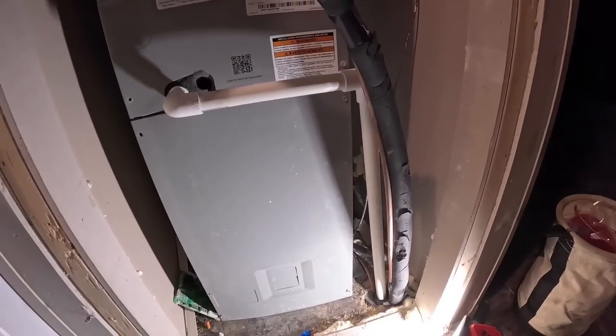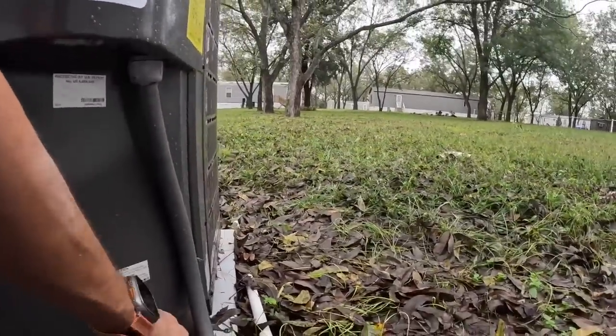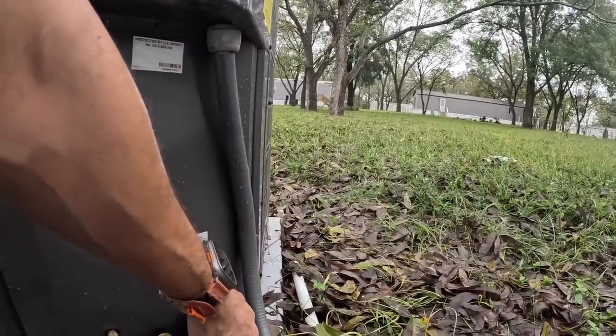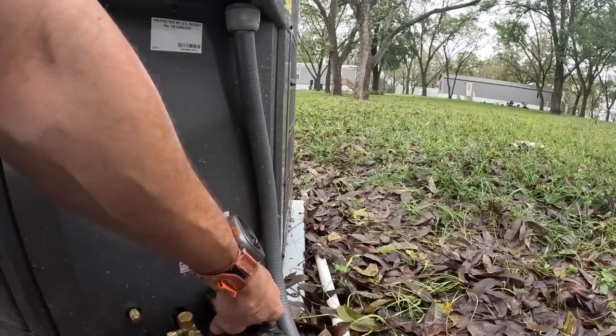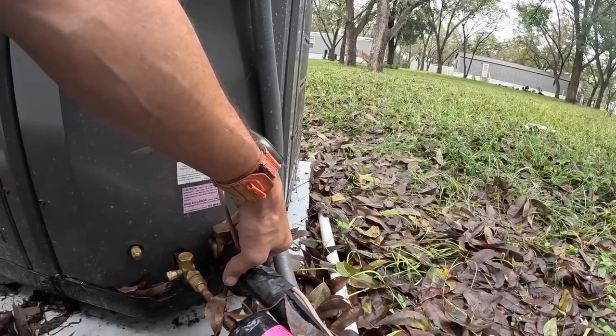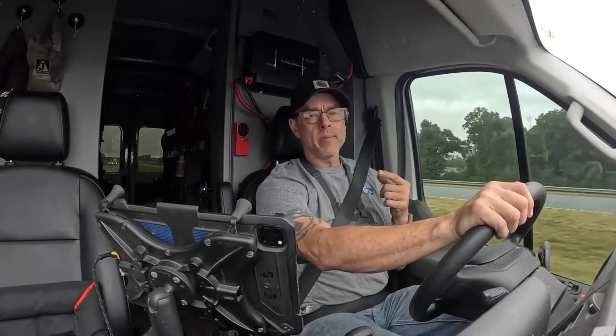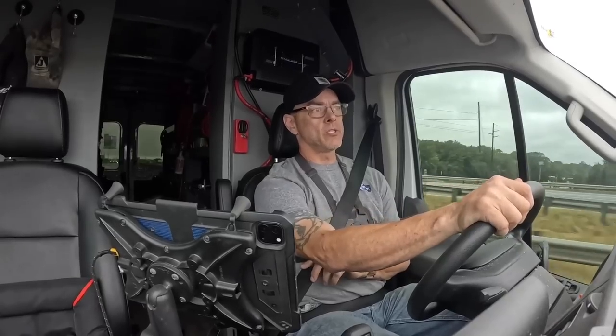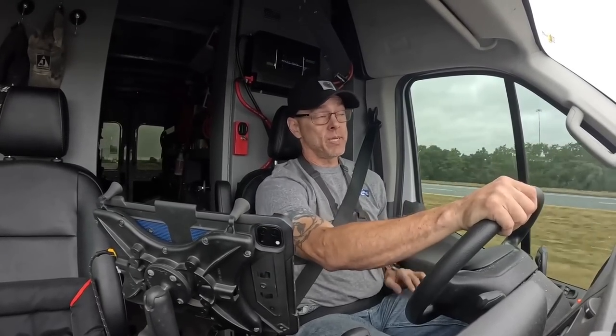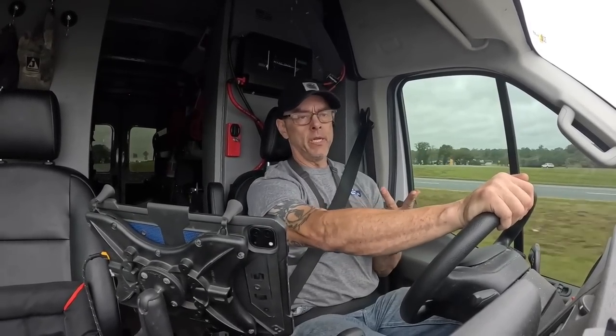Let's see about cooling. Check pressures on this. It's probably been 2 weeks ago now, and the pressures were fine. I just wanted to make sure it would come on. Well, guys, I want this video to be about changing the blower motors and how to wire them. The way I wired that one worked out just fine. I am going to have to replace the heater kit on that, but heat pump, blower, cooling, heat works just fine.